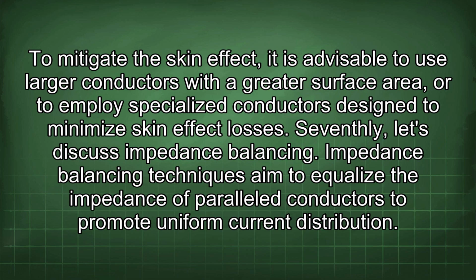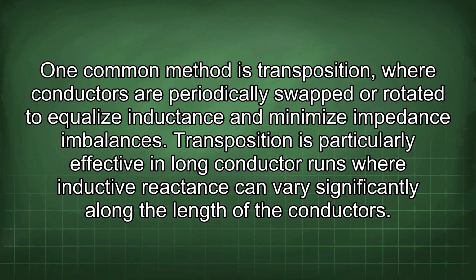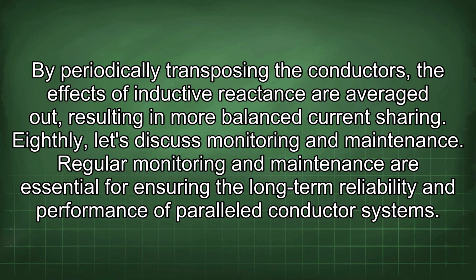Seventhly, let's discuss impedance balancing. Impedance balancing techniques aim to equalize the impedance of parallel conductors to promote uniform current distribution. One common method is transposition, where conductors are periodically swapped or rotated to equalize inductance and minimize impedance imbalances. Transposition is particularly effective in long conductor runs where inductive reactance can vary significantly along the length of the conductors. By periodically transposing the conductors, the effects of inductive reactance are averaged out, resulting in more balanced current sharing.